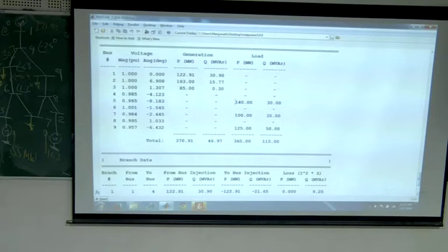Now you can see the power demand here is 140 and then the voltage is maybe this one. The angle is even lesser. So earlier the angle was how much? On the board you can see -4, but now the angle is -8. So even the demand is higher.